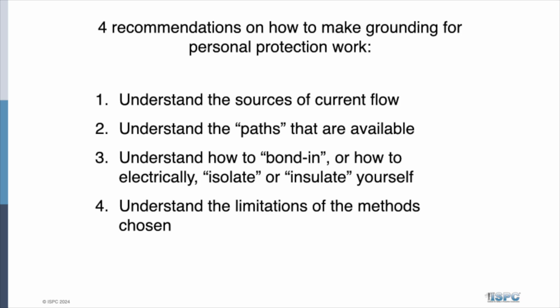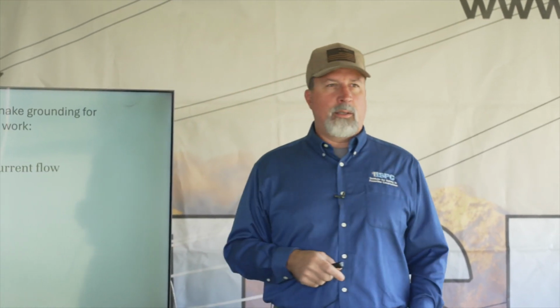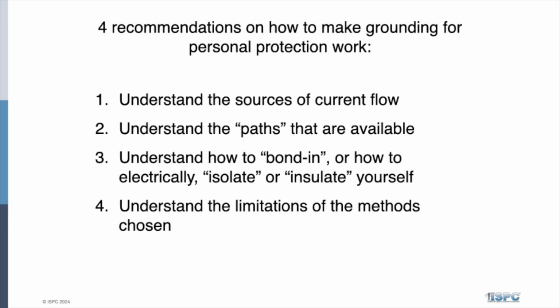So we talked about it, understand the sources of current flow. Understand if something does go wrong, where's current going to flow in this system I just installed grounding on to protect myself. Make sure that you have your grounds and your bonds installed properly to minimize that potential. Understand the paths that are available, including you, you're a path. Depending on what you're touching, when a fault or induction or an accidental re-energization happens, understand where the paths are that voltage and current can flow so that you can protect yourself from those. And again, you're one of those paths.